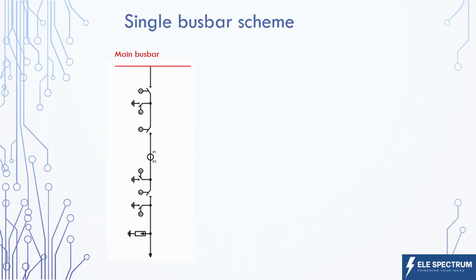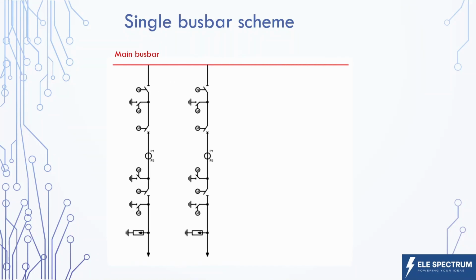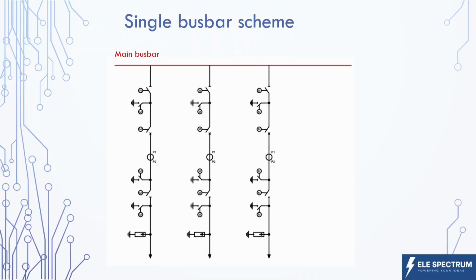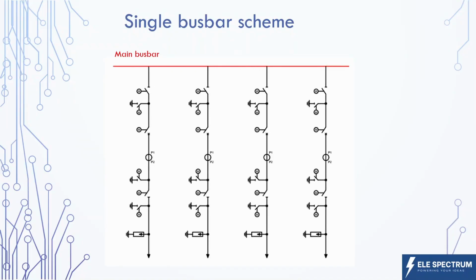In our last video, we discussed how to construct a feeder: disconnector, earthing switch, CTs, surge arresters, right? Let us consider the same feeder as you can see here. And now let's just extend the bus bar that we have here, and we put more feeders connecting to the same bus bar. And we have our first bus bar arrangement, which is single bus bar scheme. These feeders could be anything depending on your substation configuration, for example, distribution feeder, transformer feeder, or capacitor bank feeder.